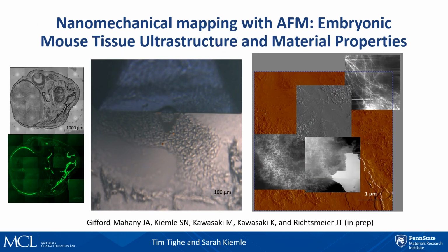Another example of applications for the atomic force microscope is nanomechanical mapping. For nanomechanical mapping, you don't only get the height or the topography, you also get your mechanical channels. You get modulus, adhesion, indentation, deformation, and many more.